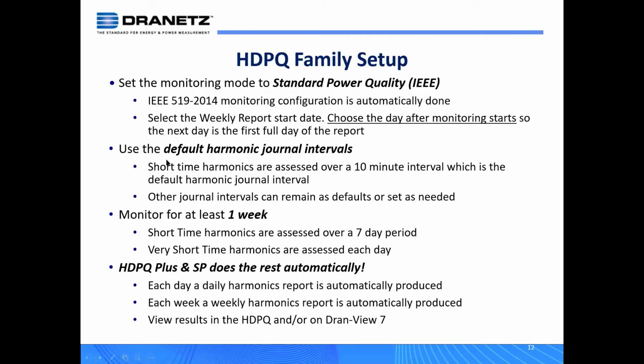So just to note, use the default harmonic journal intervals. The instrument sets itself up to a 10-minute journal interval for harmonics. That is the instrument default. You, of course, can change that, but this is part of the short time harmonic assessment that's required by 519-2014. So this is kind of hands off. You really don't have to touch anything else in the instrument.